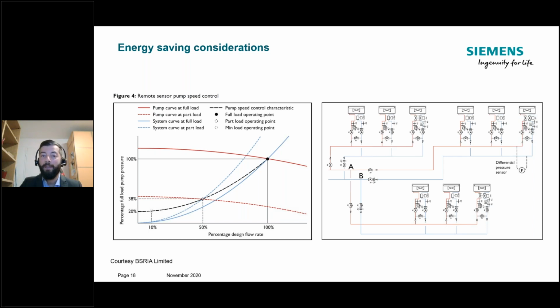We could speak maybe for hours about this, but to make it short, imagine a system like this one, and then you install a differential pressure sensor somewhere nearby the least favorable circuit, and this sensor communicates back with the pump. So this method could be called remote sensor speed control, where the pump is driven according to the signal of a sensor which monitors the trend of the delta P at a specific point of the system, called the index circuit. Or in reality, people place these sensors somewhere close to it.